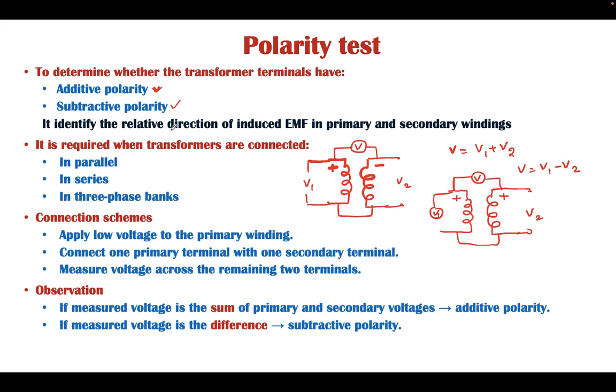Now it identifies the relative direction of the induced EMF in the primary and secondary winding. Why do we require the polarity test? Because sometimes we need to connect transformers in series or in parallel, or there is a three-phase transformer bank, and in that case we need to find out the polarity of each phase. Now these are the connection schemes for how we can perform this polarity test.